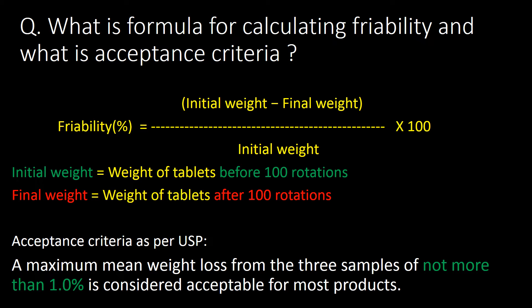What is the formula for calculating friability, and what is the acceptance criteria? Percent friability is calculated as: initial weight minus final weight, divided by initial weight, multiplied by 100. Here, initial weight refers to the weight of tablets before 100 rotations, and final weight refers to the weight after 100 rotations. The acceptance criteria as per USP is a maximum mean weight loss from 3 samples of not more than 1%, which is considered acceptable for most products.